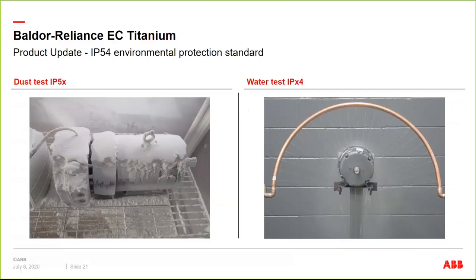IP54, I just wanted to touch on this. This is what an IP54 test looks like. You have an independent certification company that does the dust test. You have to pull a vacuum, which is what this hose is, on the interior of the motor, and then you can't get any dust inside the product. And then the water test is basically water hose pressure, like a sprinkler system, and you have to spray it at various angles as you rotate the motor. And you put a water sensitive dye inside, and when you open it up, none of that dye can have turned to a blue color. It's white to begin with, so it's very easy visually to see if any water gets in. So it is a fully IP54 tested product.